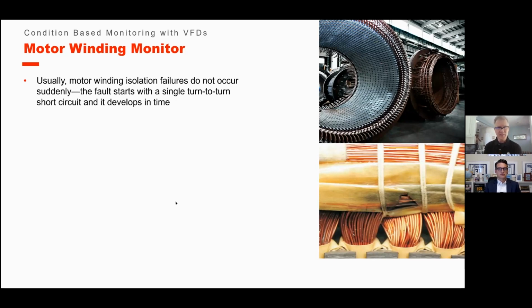So when you look at the inside of an electric motor, you have a bunch of wires, special coated magnetic wires, mag wire, and they have insulation on them. They'll have VFD insulation, and they'll have regular insulation besides. But as that motor gets power, that winding likes to move. And you do dip and bake it with a process. We're not going to get into motor theory here, but with that process, you still have movement. And as load and spikes come through, you have a lot of abrasions, and you do get overloads and that type of thing.